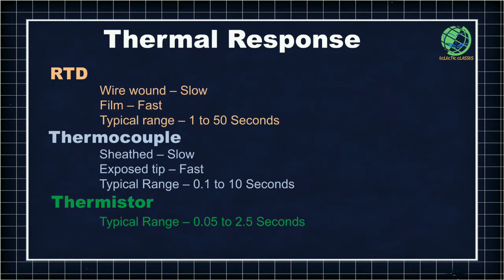When it comes to thermal response, thermistors have the fastest response time at 0.05 to 2.5 seconds. RTDs are the slowest among these three, with a thermal response time of 1 to 50 seconds. Thermocouples lie in between, with a thermal response time of 0.1 to 10 seconds.